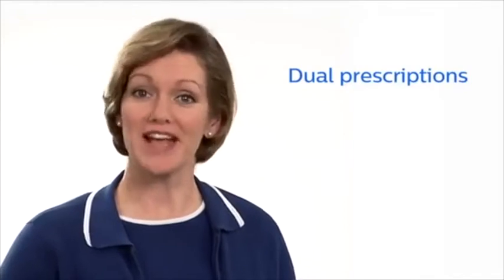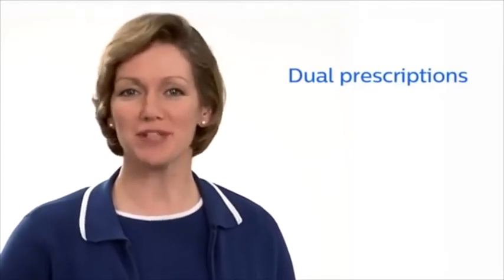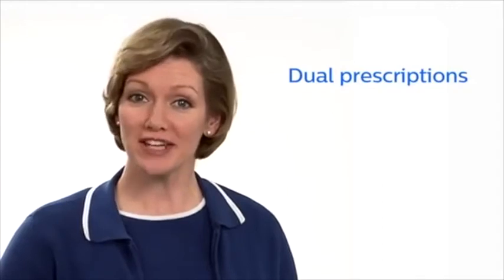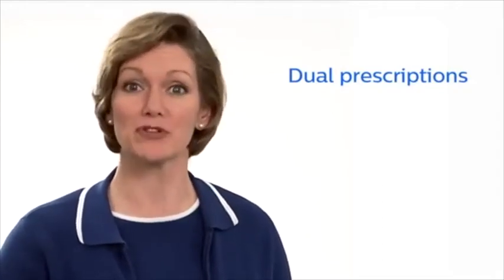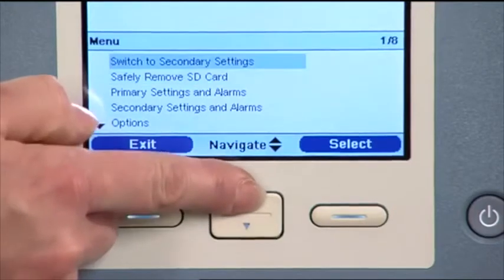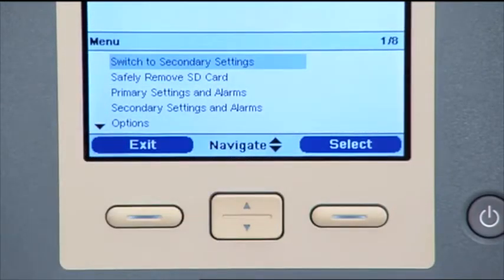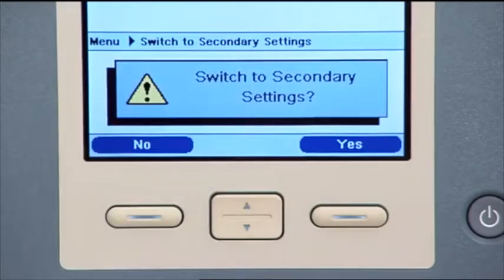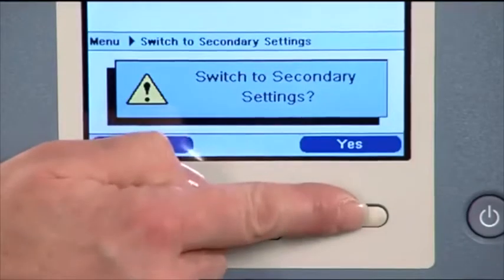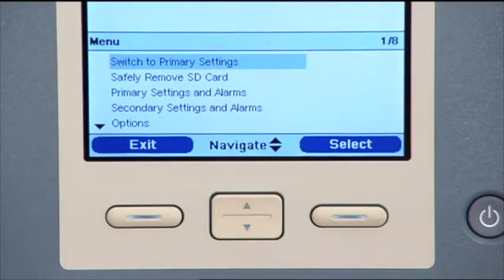If the home care provider has set up a dual prescription, this option will appear on the menu screen. You can change to either your primary or secondary prescription settings. Use the Center Up-Down button to highlight the Switch to Primary or Switch to Secondary options. Press the right button to select it. Trilogy 100 will ask you to confirm that you want to make the change. You can press the left button to answer no. In this case, I'll press the right button to answer yes and switch to the new prescription. The display screen returns to the main menu after a selection is entered.